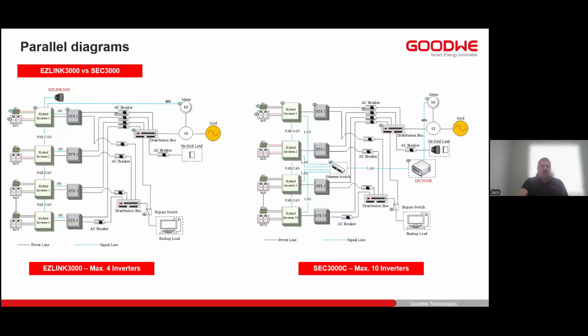Then we'll take a quick look at parallel operation. There's two ways of paralleling the ET50. The first way is with the EzLink 3000 dongle. This way we can achieve 4 inverters in parallel with only adding one EzLink dongle. The EzLink dongle then becomes the master. So whichever inverter the EzLink is plugged into will become the master inverter, and up to 4 units can then be paralleled, meaning 200 kilowatts, and that will achieve UPS level switching.